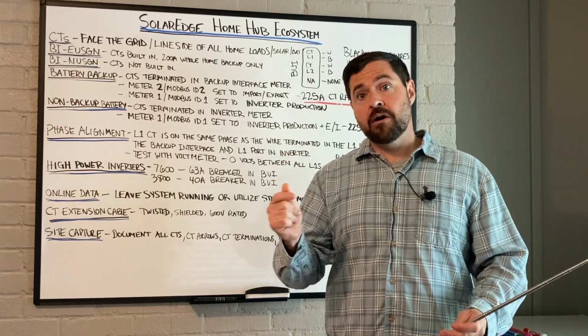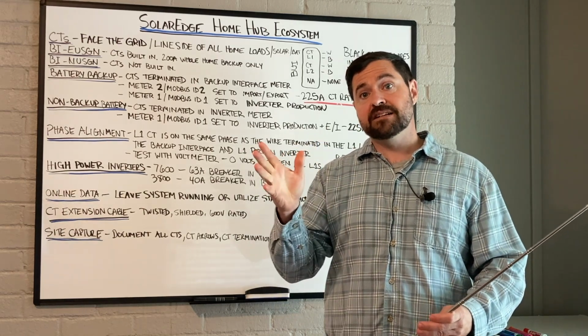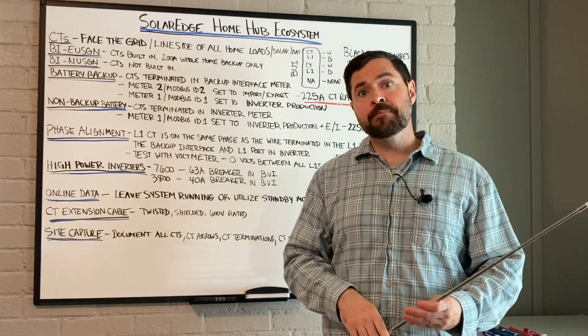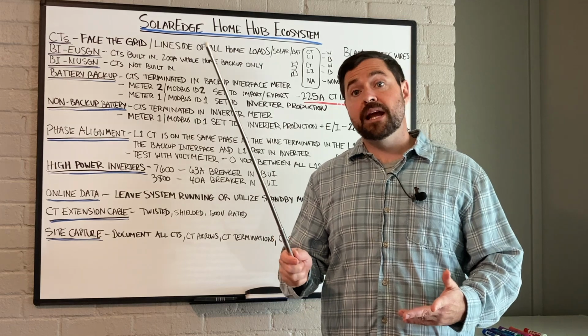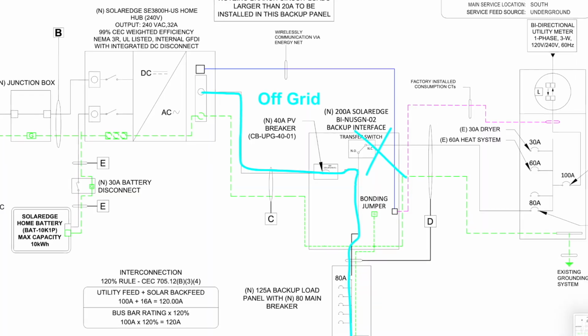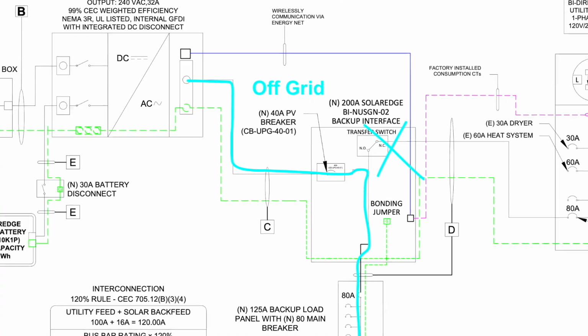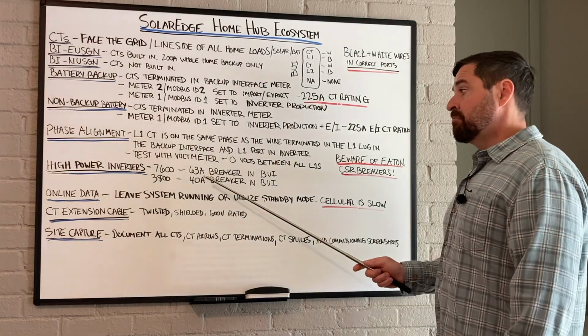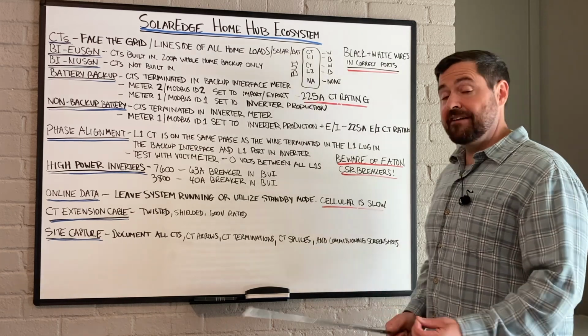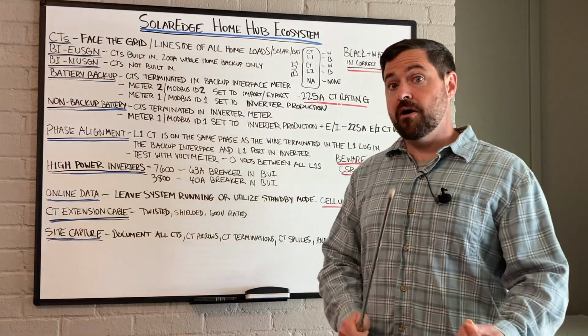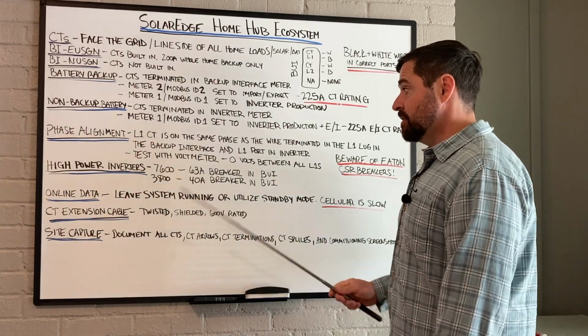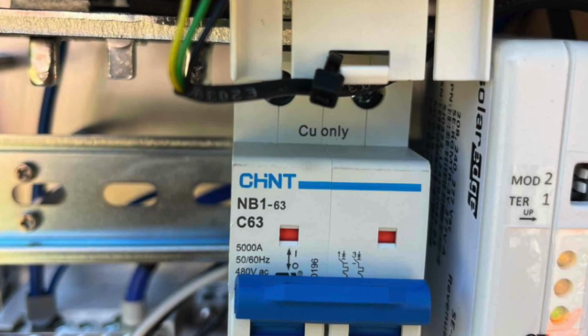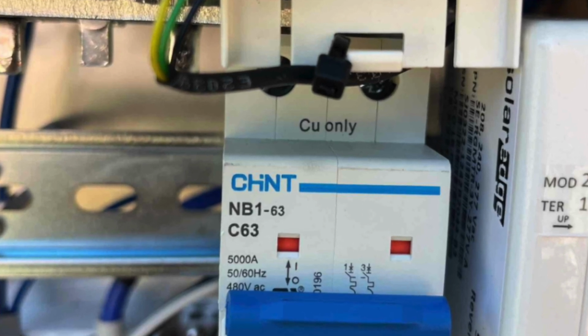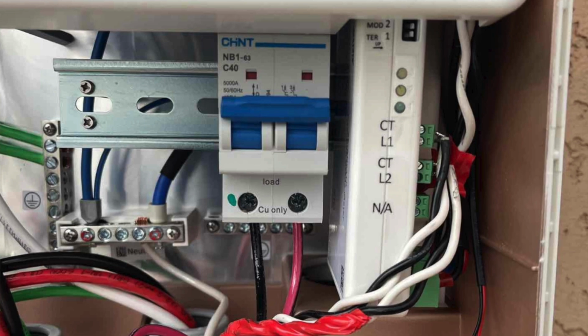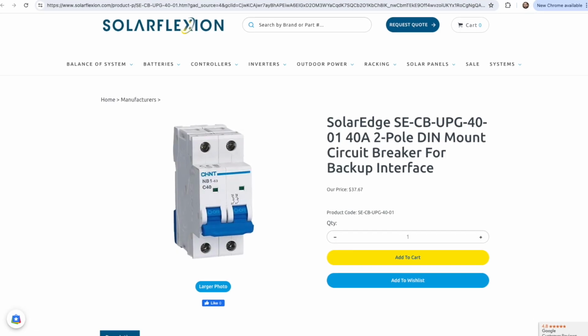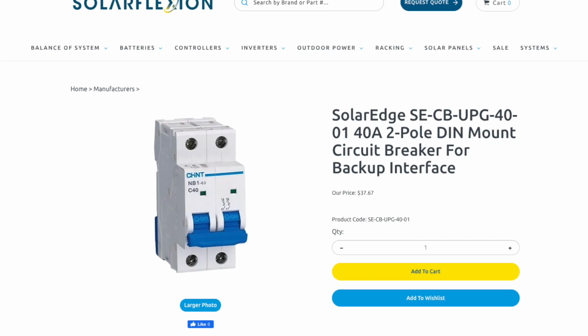But the moment it goes off grid and the backup interface disconnects the inverter from the main service panel, it can send up to 43 amps continuous from the solar inverter through the backup interface to the backed up loads panel. And for that reason, those breakers inside the backup interface have to be sized appropriately for that off-grid current. So for the 7600, that is going to be a 63 amp breaker in the backup interface. And for the 3800, that's going to be a 40 amp breaker in the backup interface. And those are a very specific type of breaker that you will need to pre-order in advance of the installation.